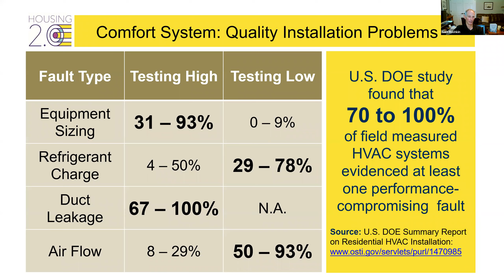Refrigerant charge was low 30 to 80% of the time. Duct leakage occurred in two-thirds to 100% of homes tested across various markets, and airflow was an issue in 50 to 93% of homes. That's staggering. It's an epidemic of low quality HVAC installation.